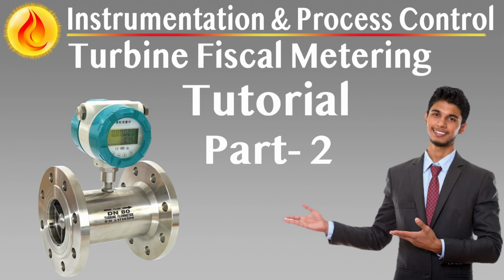Field instruments must be rated for ambient temperatures ranging from minus 65 degrees Celsius to plus 55 degrees Celsius, with resistance to condensation, precipitation, ice formation, and wind speeds up to 30 meters per second. They must also withstand high humidity levels up to 100%, salt spray in coastal locations, and airborne chemicals such as hydrogen sulfide or ammonia. Housings must be weatherproof, corrosion resistant, and sealed to prevent ingress of dust or water. Stainless steel, minimum 316, is required for all junction boxes, mounting hardware, and cable trays.